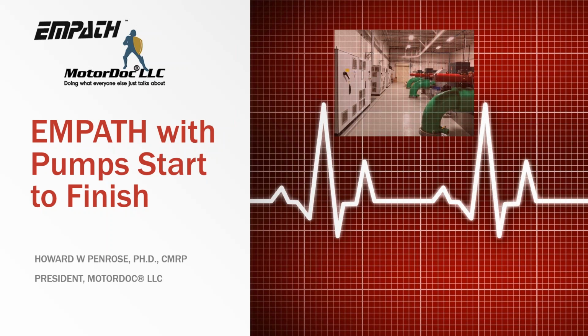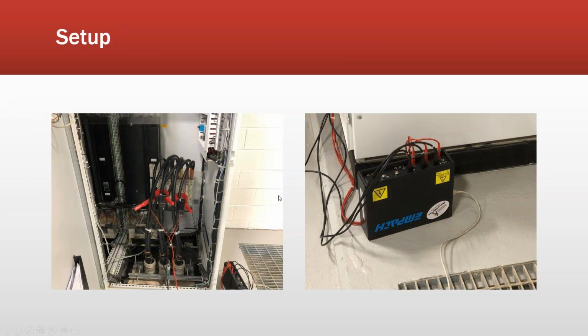So in any case, here is the system setup that we're going to be analyzing. This is the VFD on the output. One thing I want you to notice is I put a current clamp around 1 of 3 on each one. Okay, so that'll be important when we set up our CT ratio. Now yes, I could have probably gotten around 2, but really that makes it really strange when setting up that ratio. So just around 1, still get good results.